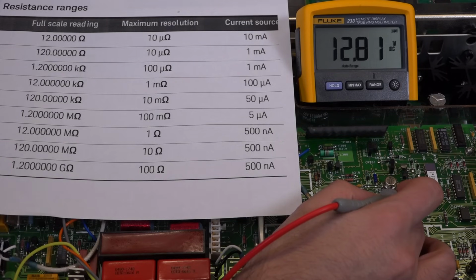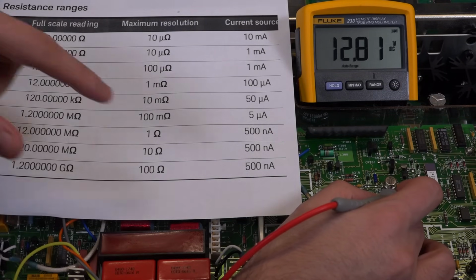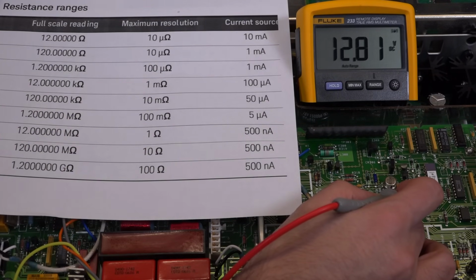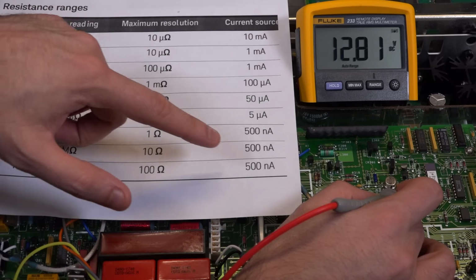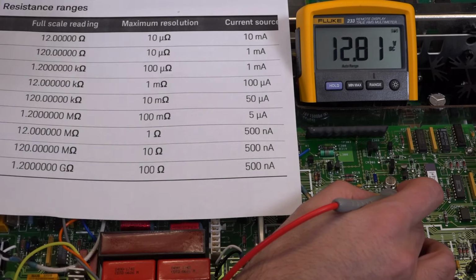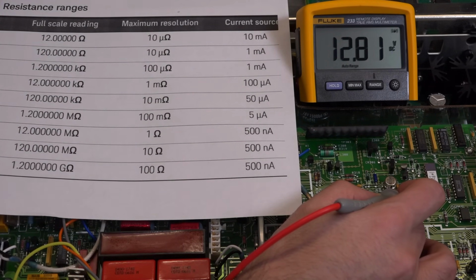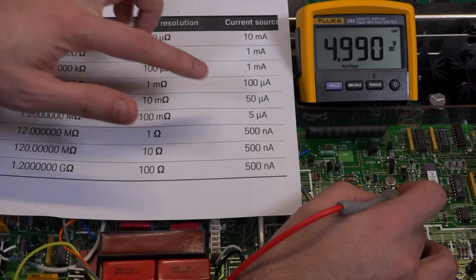So here I'm measuring the gate voltage on the lowest current, which is the highest range over here, and I'm going to step back. Eventually, after changing the range 3 times, I should have that signal disappear, hopefully. So there we go. So as 1, it should stay. 1 more time, it should stay. And now, there you go, look at that. It does disappear. And now the next range is the 5 microamp range.